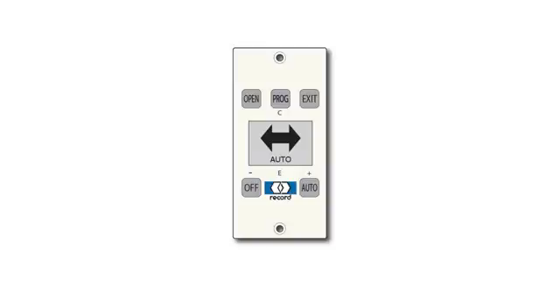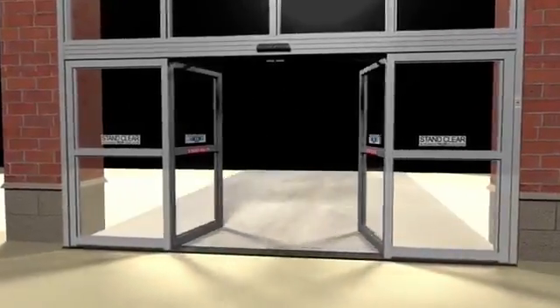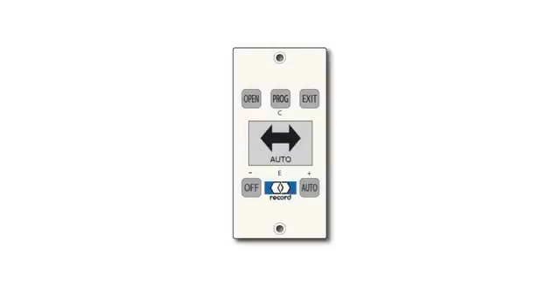The Smart Panel will display 'Emergency Stop Breakout' when the door is in the emergency breakout position. This can happen unintentionally when pedestrians run into the door while passing through it. Securely returning the door panels to their original position will allow the door to begin operating normally.